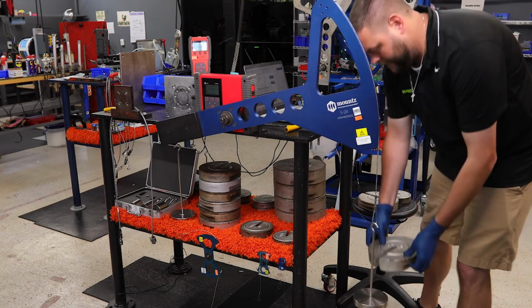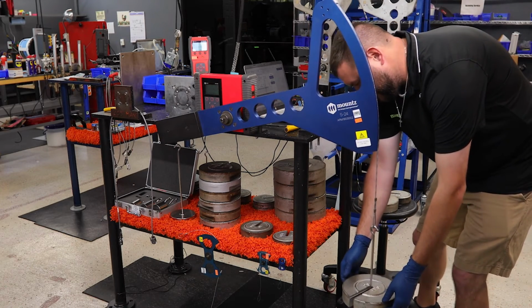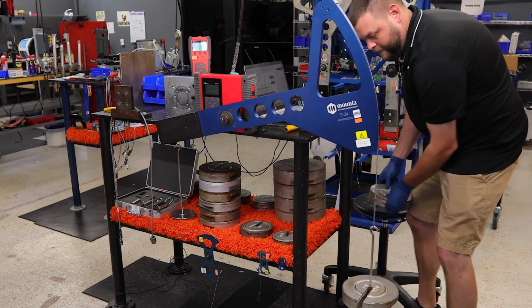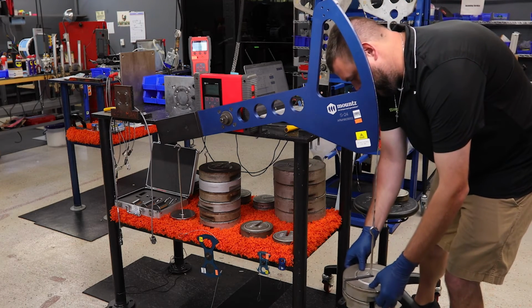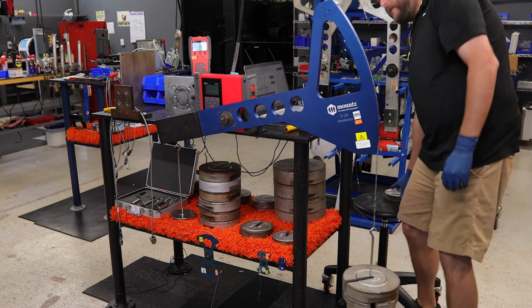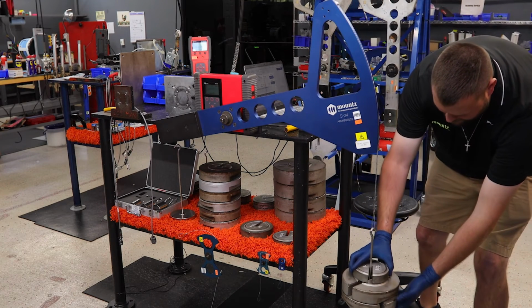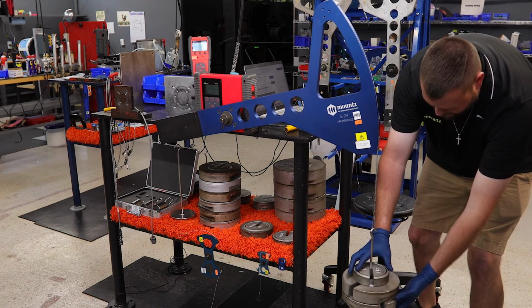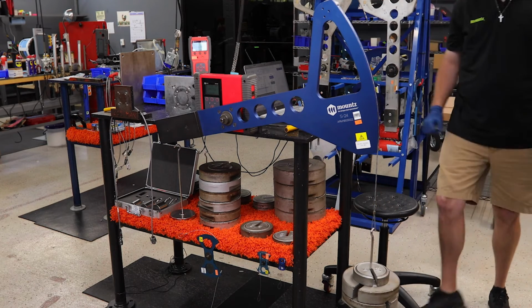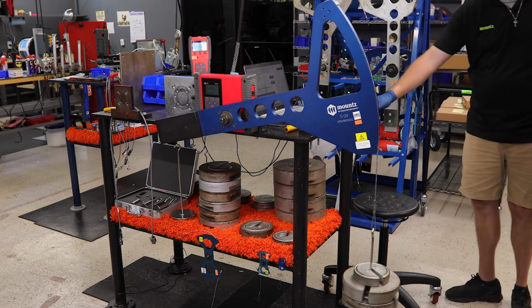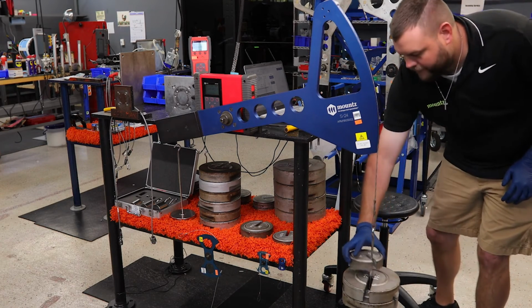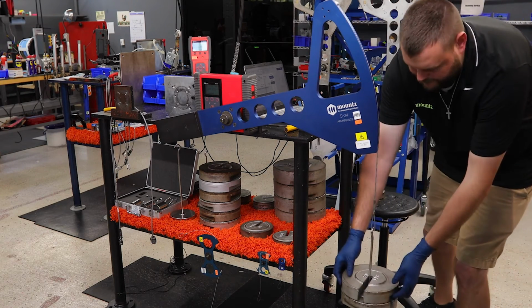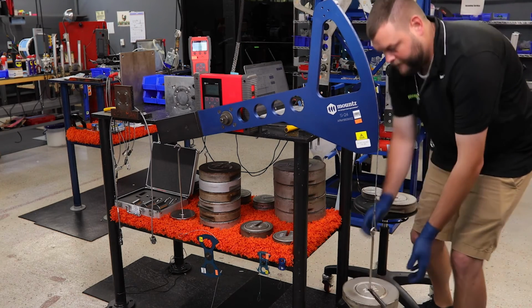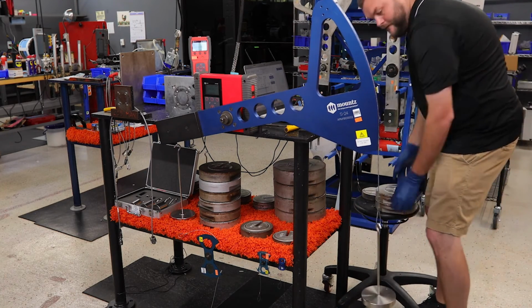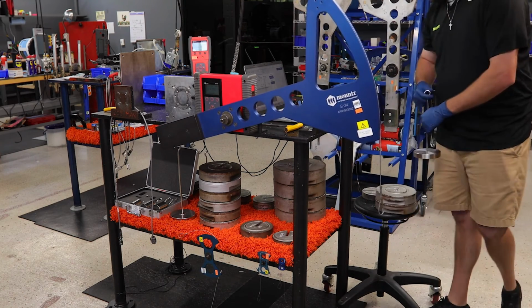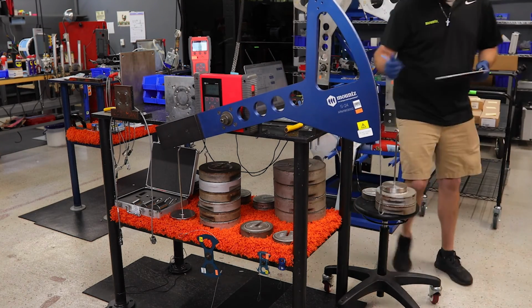So our hanger is 5 pounds. We have 2 plates that are 20 pounds and then 1 additional plate that is 5 pounds. So at first, we load the sensor to 100%. This allows the sensor to be exercised. So we let that hang for 30 seconds to a minute. I have cut the waiting time out of this video, so we can move the presentation along without unnecessary waiting.